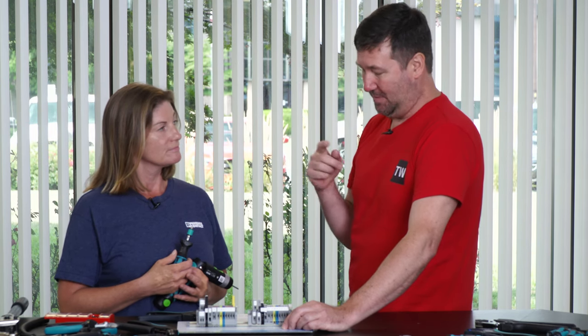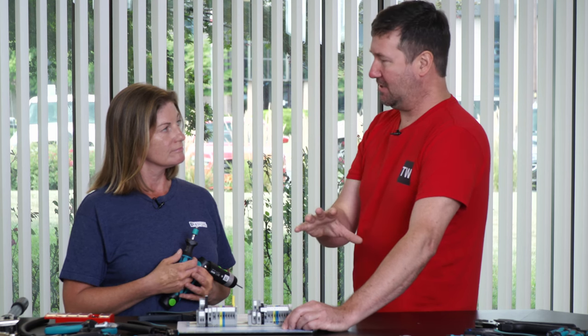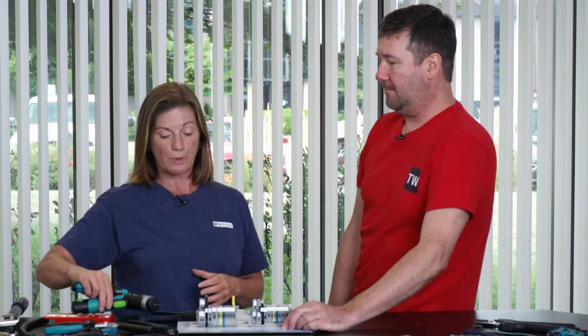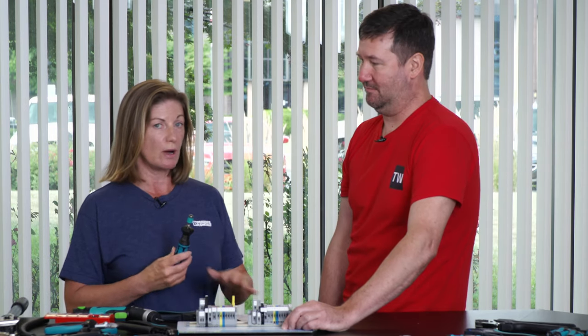And all tools that you use to torque in a UL panel have to be calibrated. Correct. What does calibration entail? Do they need to send it back to the manufacturer to do that? No, there's always third-party local businesses that will calibrate the tool. Also note that UL requires it to be calibrated or tested for calibration annually.